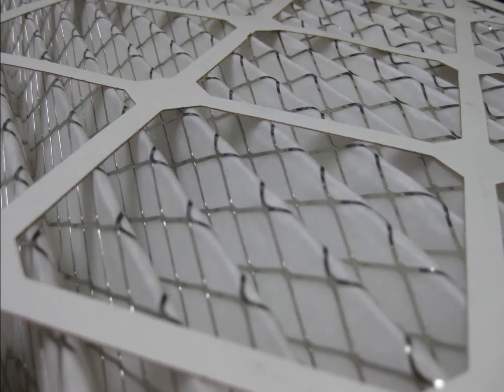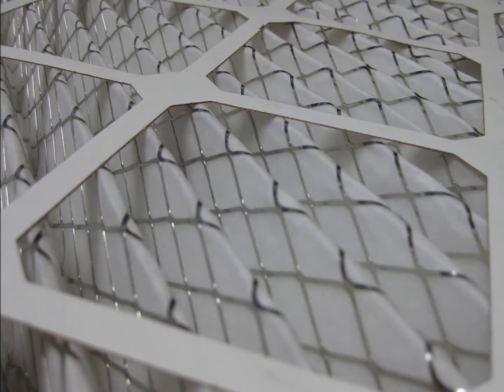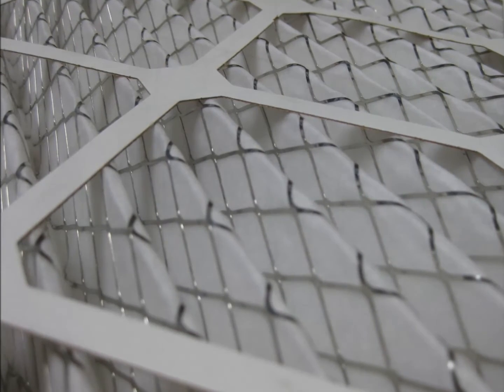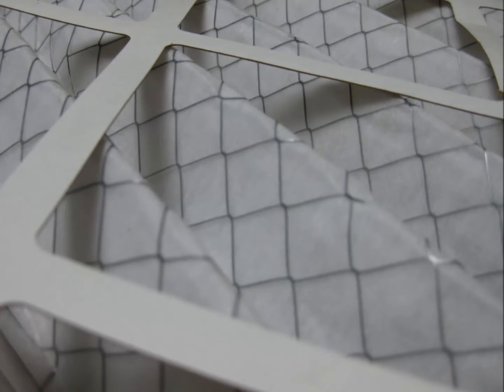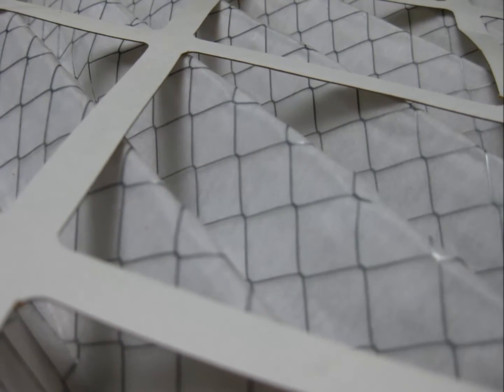Support for the filter's media has multiple variations as well — from the most durable welded wire grids, to pleats that have no support at all, called self-supported filters. Cell-supported filters are certainly a cheaper production method, but not very durable in the real world.